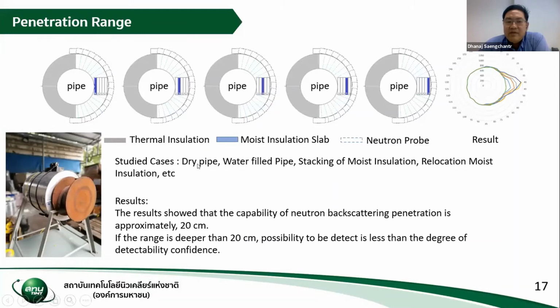Then we try many cases. For example, a dry pipe, a pipe 100% filled with water, and we stack the moist insulation or relocate the moist insulation as well. And we move the probe along the periphery of the pipe, all sides along the whole circle. Then we plot like this. So you can see that if we put the water near the surface of the probe, we obtain very high backscatter. On the other hand, if we put it farther away, the neutron count becomes lower.